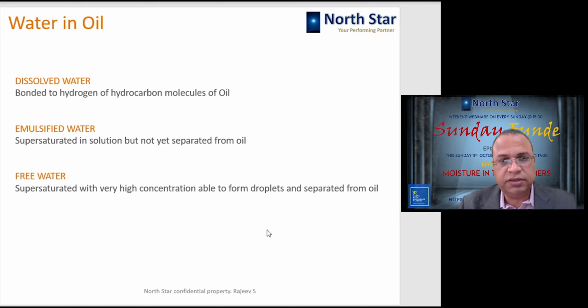So if your oil looks like it is mixed with a little amount of milk, you can understand that the water content is high but it is in the emulsified state. Third state is free water, where the concentration has gone so high, it is supersaturated, that it is able to form droplets and it is getting separated from the oil. So when you see water in the oil, that is an indication that the oil is already supersaturated with moisture, and this is extra moisture which the oil is not able to carry within itself. So free water presence in the transformer is a very alarming situation, and that is talking about severe damage that must already have happened to the solid insulation of the transformer. So this is how the water behaves inside the oil.